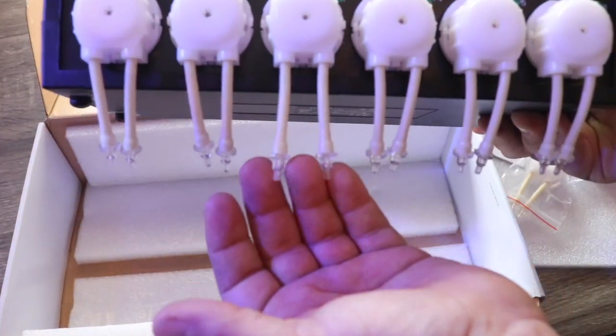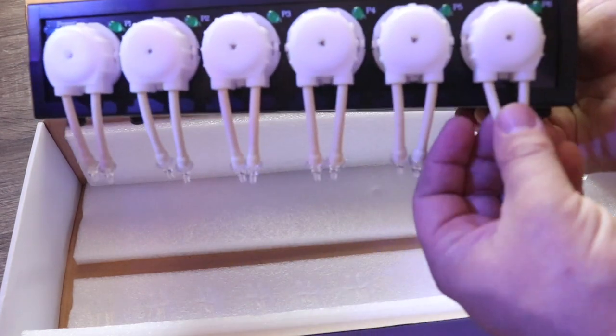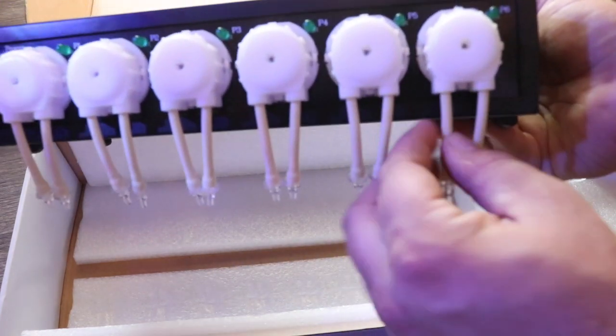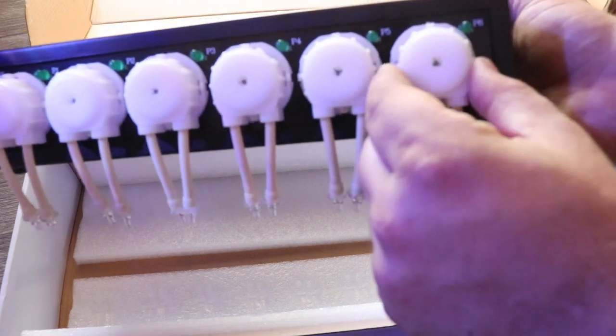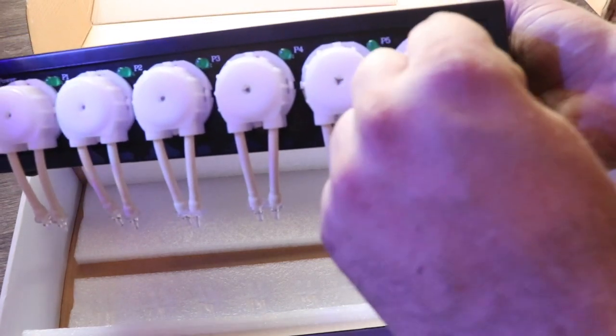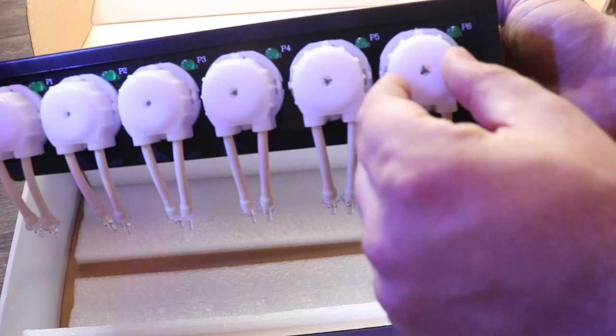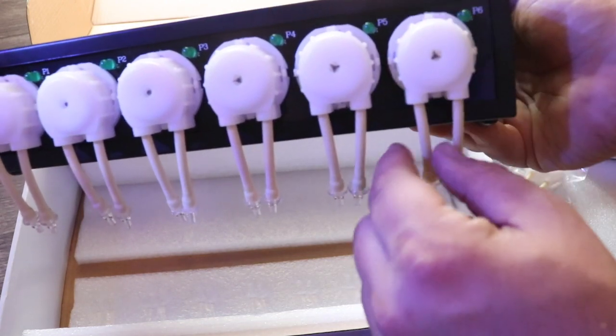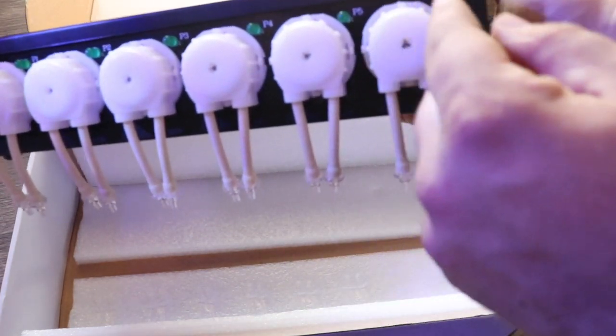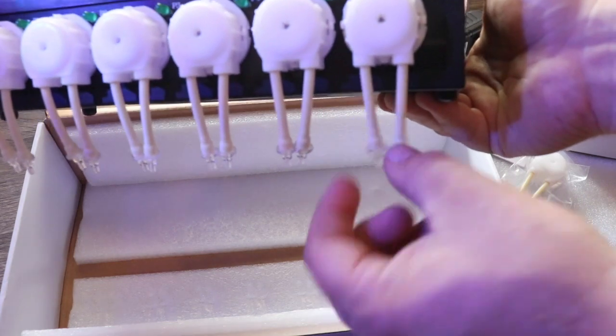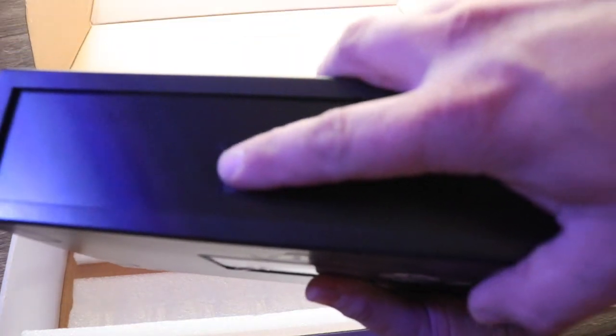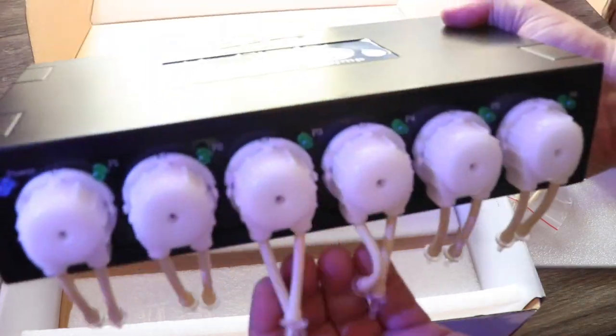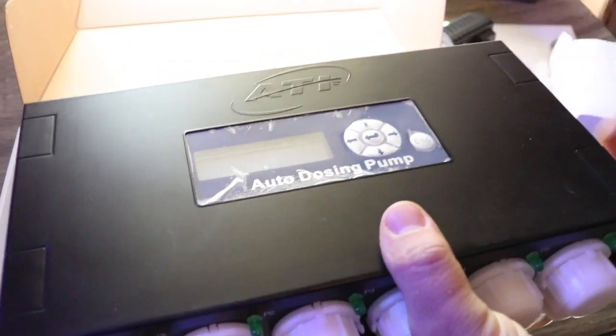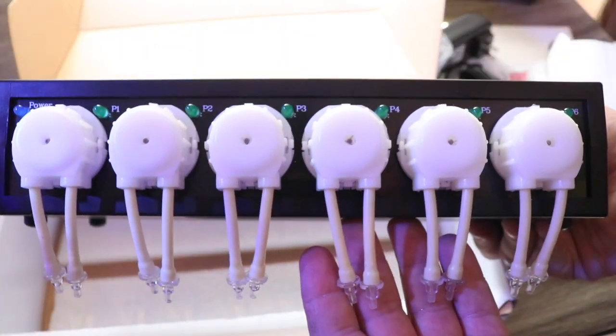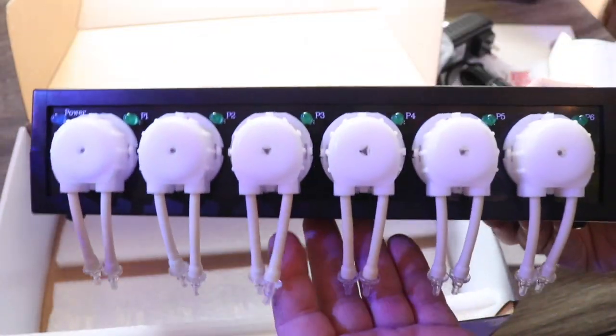They do wear out and need to be replaced because essentially what's in there is you have this tubing that goes around the outside of the wheel, and then there's 2 points that are pressing, sometimes 3 points that are pressing on that hose, and that's what's pulling the solution through the pump head. And that's where your power supply goes, right there in the back. Easy enough as far as an unboxing goes. There's nothing else there. Let's go ahead, plug this guy in, and see about setting it up and calibrating it.